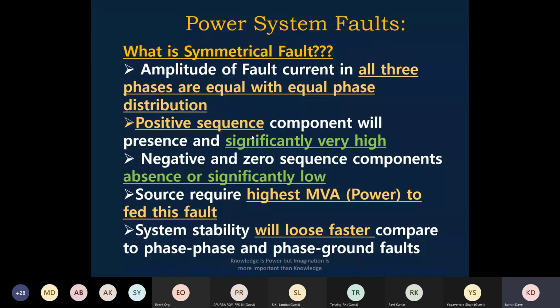When there is a symmetrical fault, as we have seen in our slides, the positive sequence component will be significantly high. Negative and zero sequence will be absent or significantly low. That is why we say it is absent. The source requires a very high MVA power to feed this fault because it is a three-phase fault, so the impedance path of all three phases goes down. The VA capacity required to feed this fault is very high, so it requires the highest MVA.